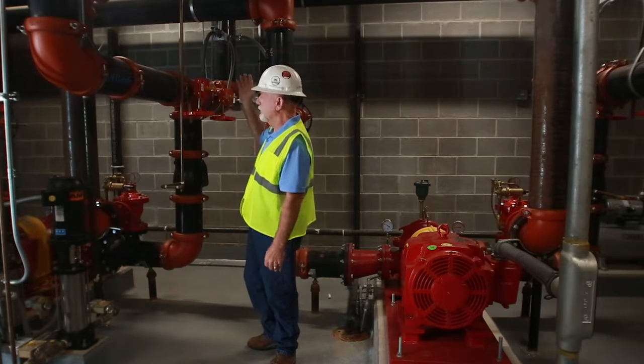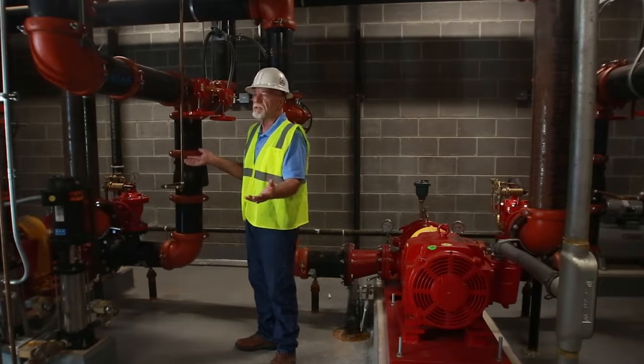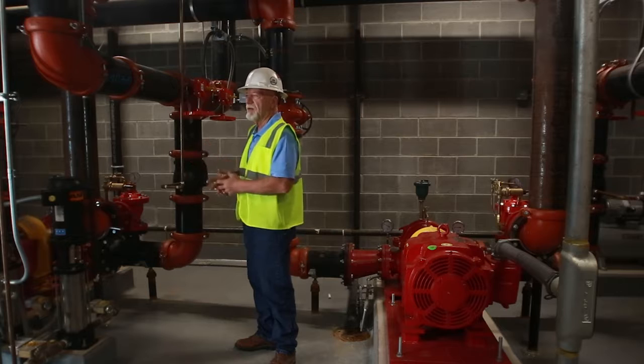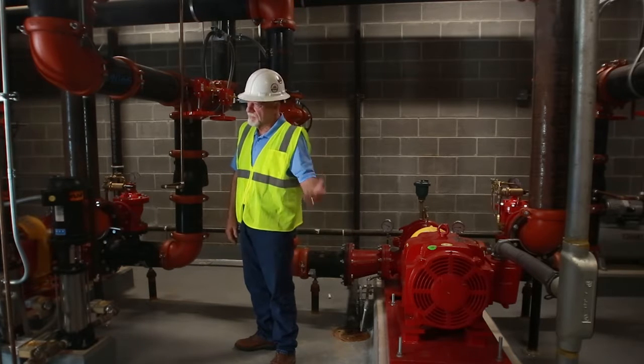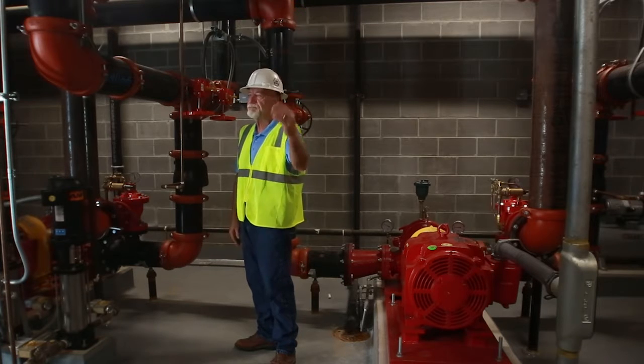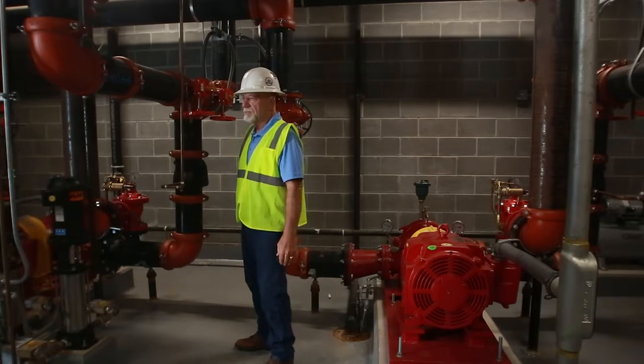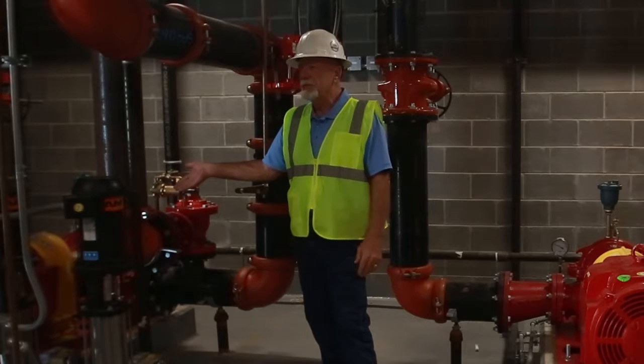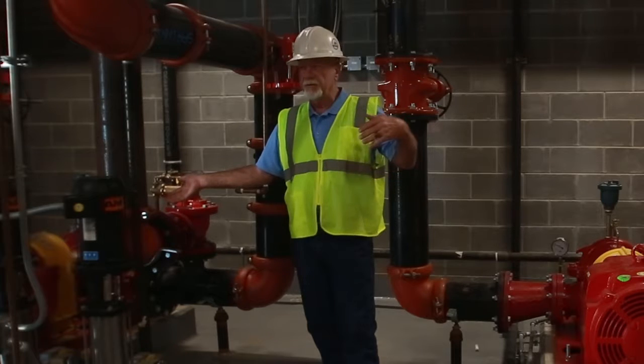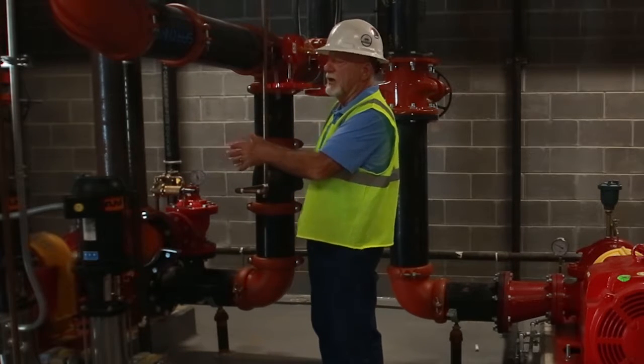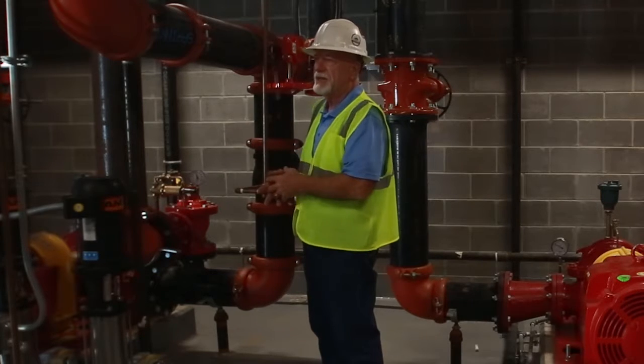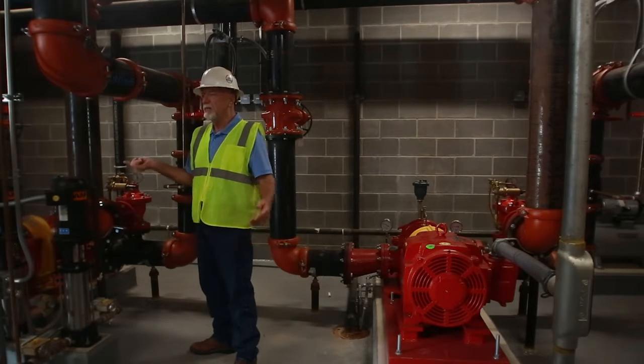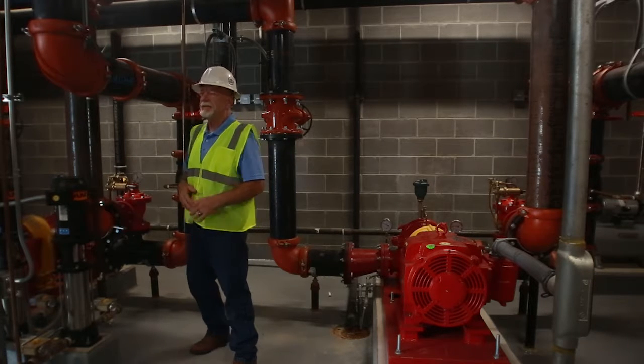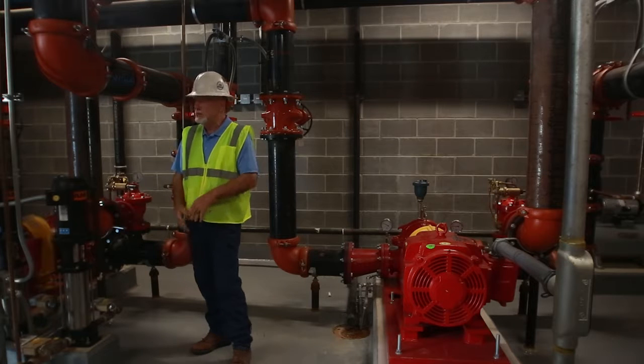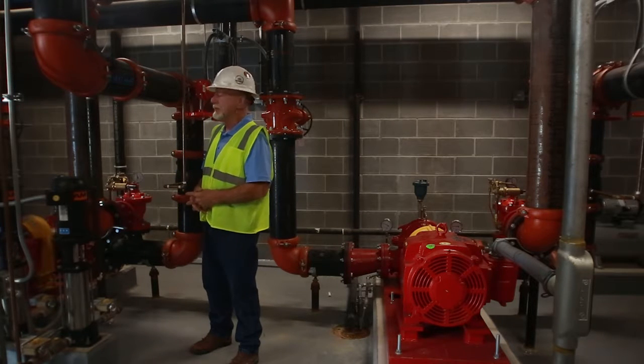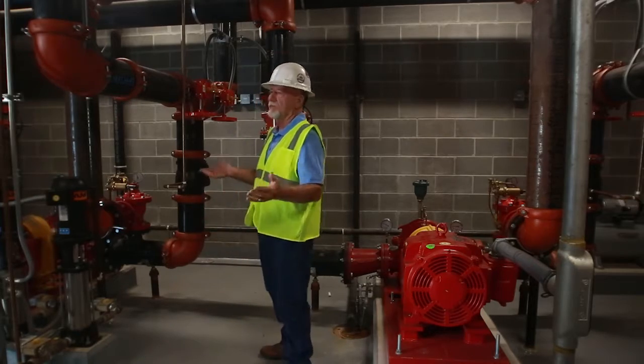So when you actually do a live flow, whoever's doing your inspections will want to do a flow, and they're going to get their 1,000 GPMs, and they're going to get 1,500 GPMs, or try to see if it'll produce that much without pulling down the static head. One of them is the primary pump, so then the other one's on sequential start. So this is the pump that's going to come on and generally run first on demand. What's going to happen is this one's going to try to keep up with whatever the event may be. If it can't, then the other pump will cut in to deliver the additional water pressure that's needed to fight the fire, whatever the case is.